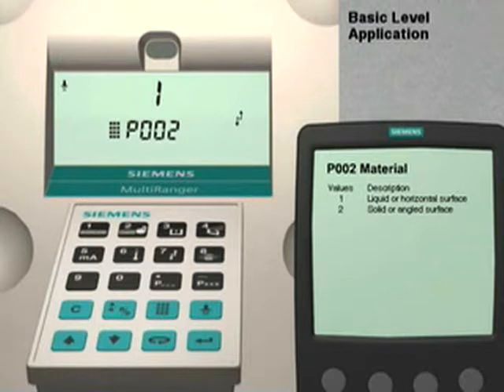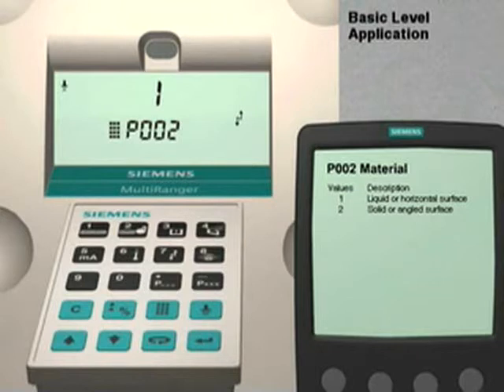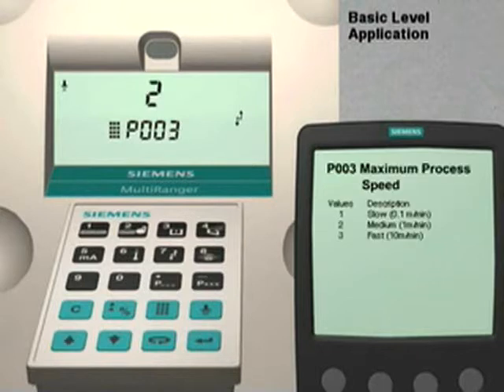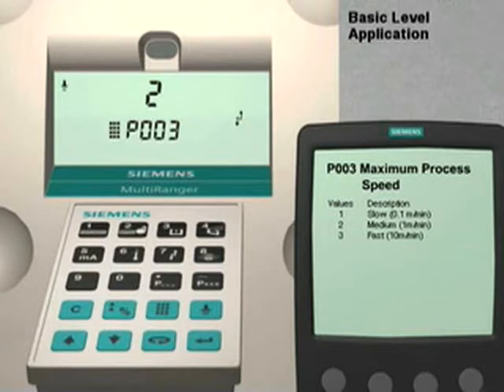Parameter number 2 optimizes the multi-ranger for measuring either liquids or solids. The factory default value is set to 1 for liquid applications. We are going to leave it at this value. Press the up arrow key to move to the next parameter. Parameter number 3 is used to match the response time of the multi-ranger to the rate of level change within the vessel. The factory default is 2 for a medium rate of change. We will leave this parameter set to the factory default.